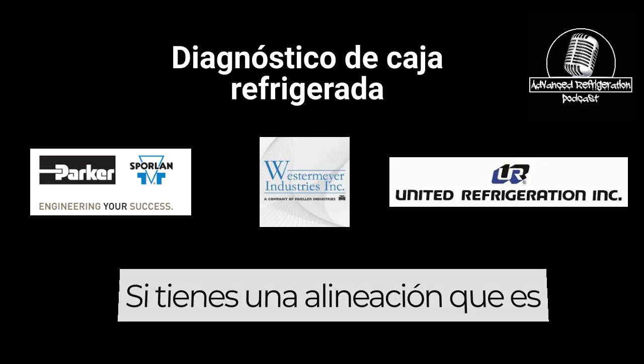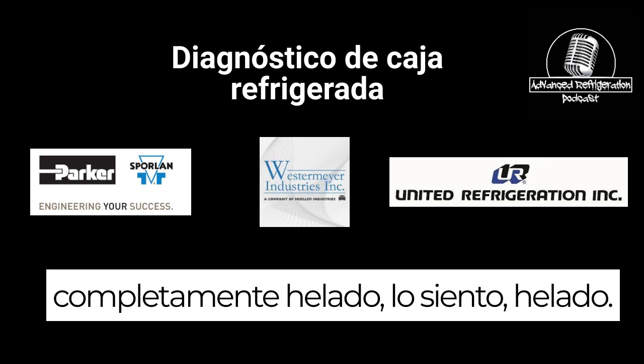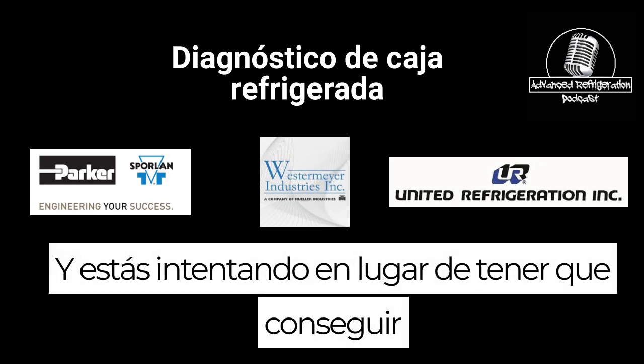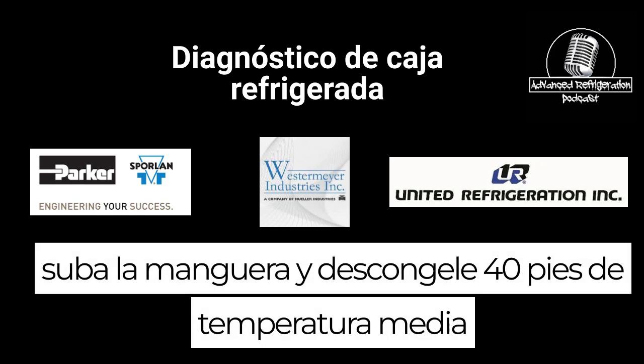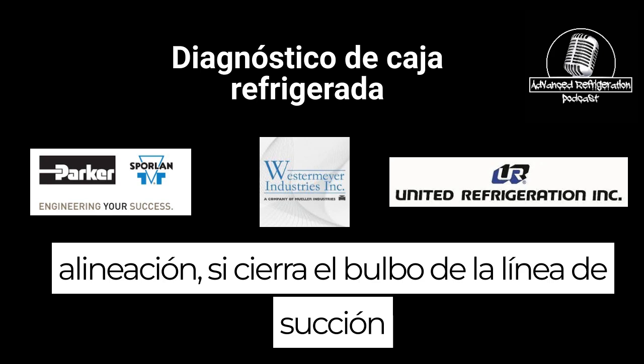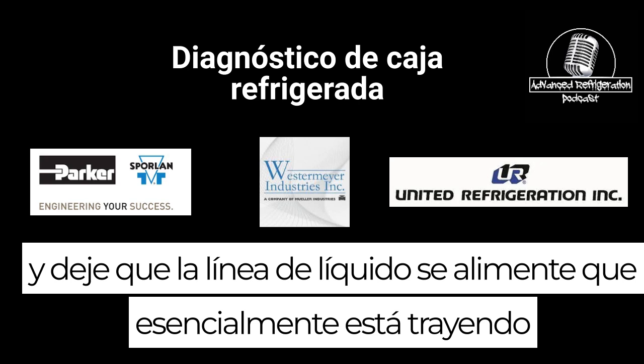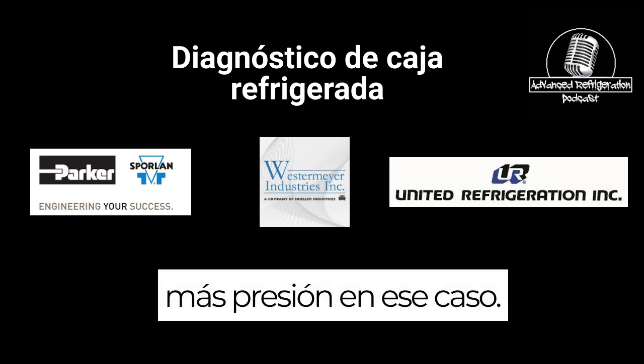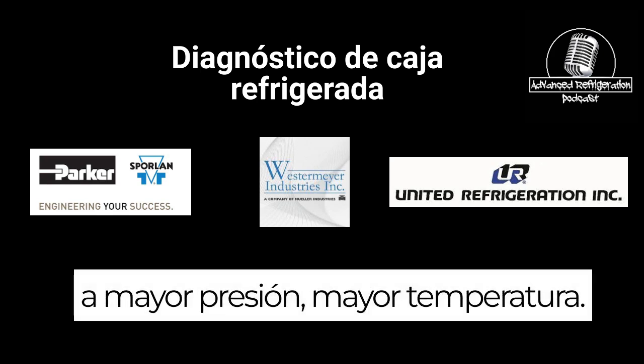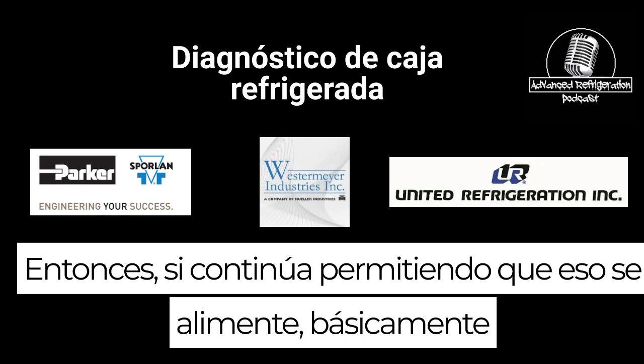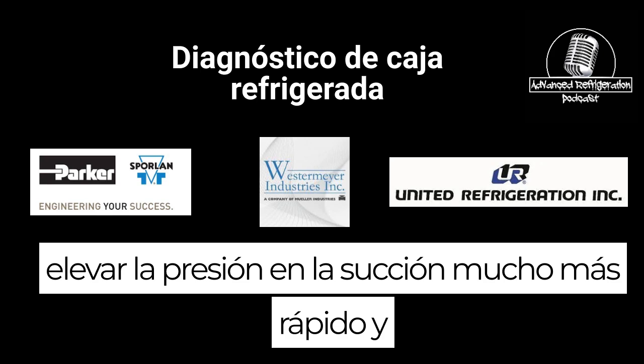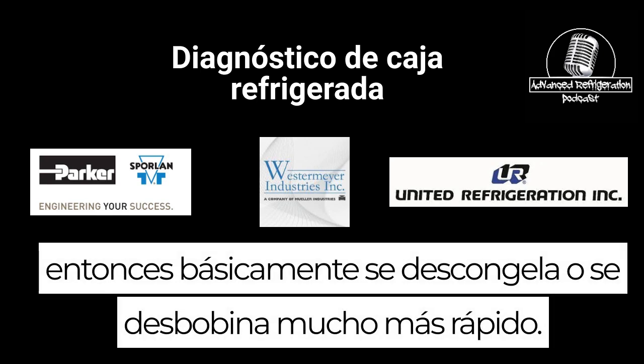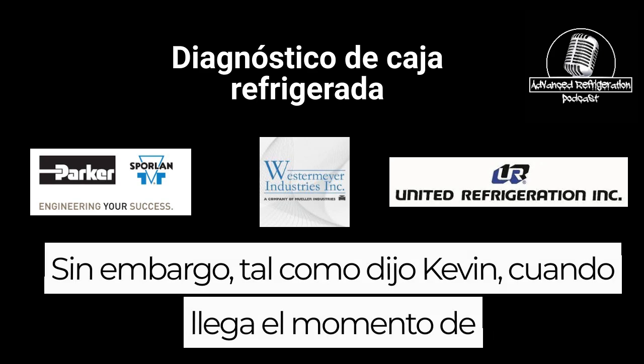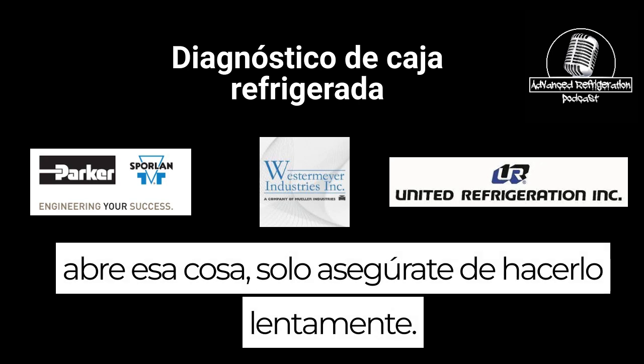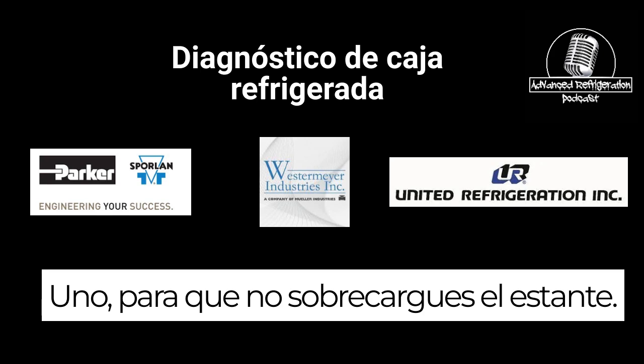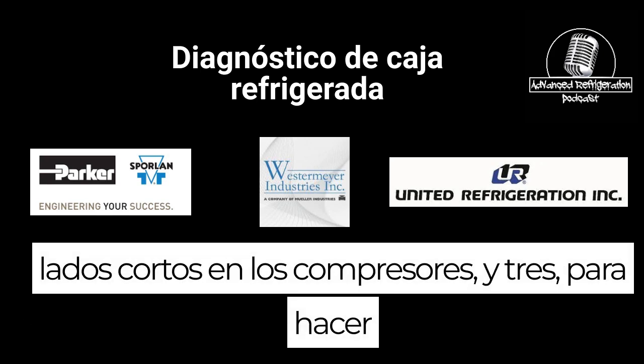One thing I forgot to bring up, if you do have a lineup that is completely iced over, frosted over, and instead of having to get out the hose and de-ice 40 feet of medium temp lineup, if you close the suction line ball valve and let the liquid line feed, you're essentially bringing more pressure into that case. And obviously, we all know PT charts, the higher the pressure, the higher the temperature. So if you continue to let that feed, you'll basically raise the pressure in the suction a lot faster and then de-ice the coils a lot faster. Just like Kevin said, though, when it comes time to open that thing, just make sure you do it slowly. One, so you don't overload the rack. Two, so you don't cause a whole bunch of short cycling in the compressors. And three, to make sure that you don't flood out your rack.